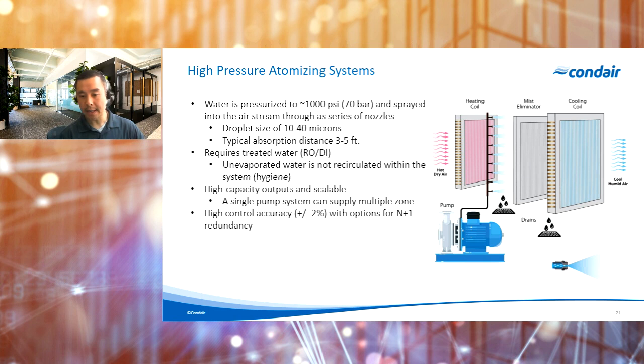So the other nice thing about the high pressure systems compared to the evaporative media systems is we can a lot of the time build these for full redundancy, so N+1 redundancy, and also have the ability to control multiple zones, each with their own set point from a single pump station. So for example, if you had 3 or 4 air handlers, each feeding different zones, each with different humidity or cooling set points, you could potentially combine those and feed them from a single high pressure pump station, but still be able to maintain individual control at each of those zones. Compared to a direct evaporative media system where we would need an evaporative system in each of those zones.